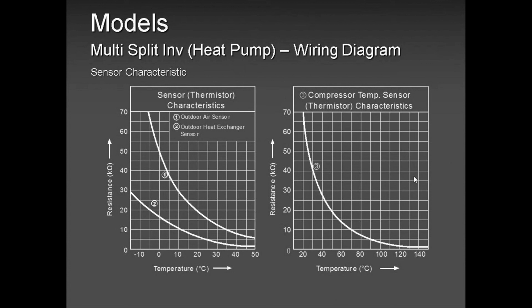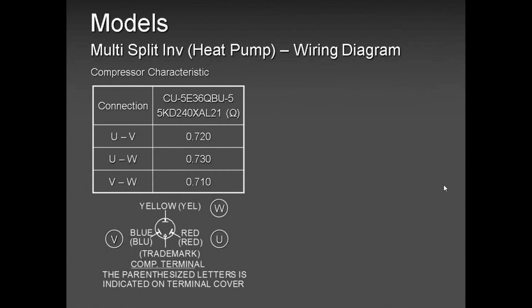Those are the sensors that are in that system. In our single zone, we have 3 sensors outside, 3 sensors inside. With our multi-zone, we have 3 sensors at the inside unit, but we have a bunch of sensors outside. We have sensors for the pipes, for all the liquid and suction pipes. Then we have a sensor for the compressor discharge and other sensors for the defrost start, the defrost end, and the ambient sensor. That's your wiring diagram. You will see it on your outdoor unit panel. On the top panel, you will find this wiring diagram.